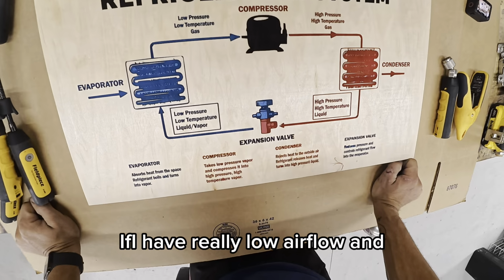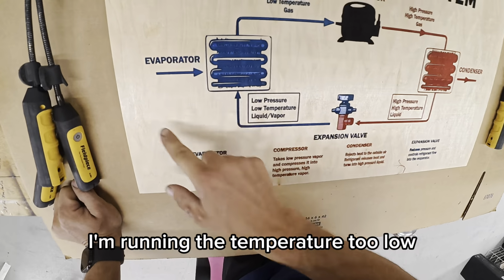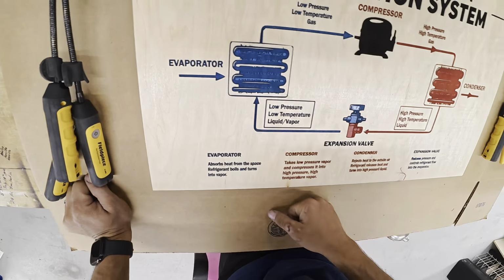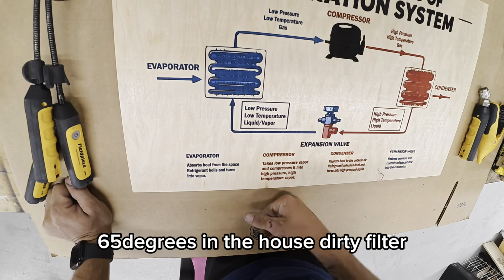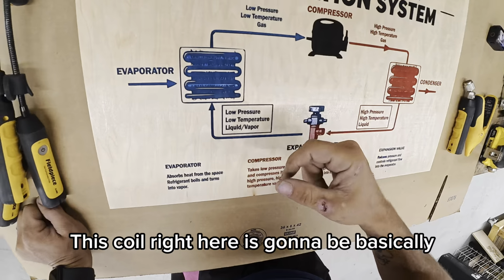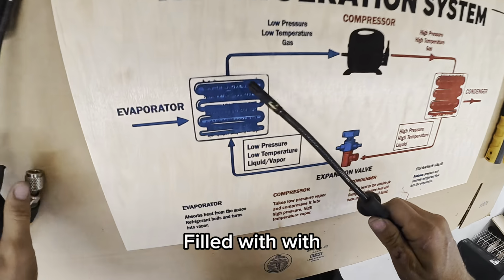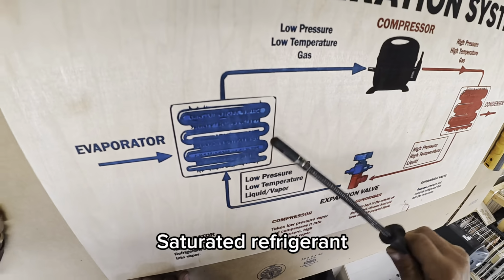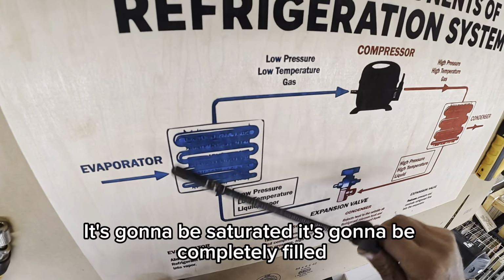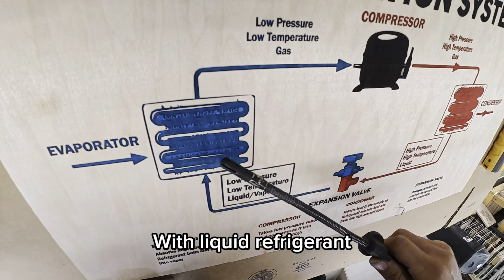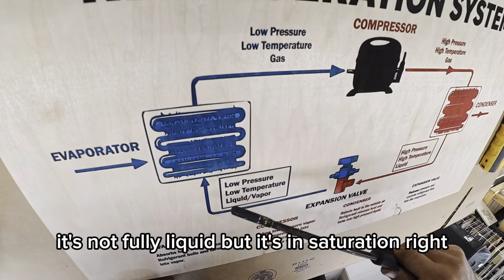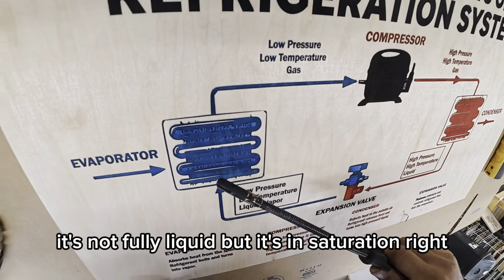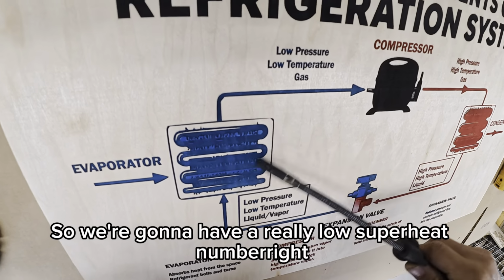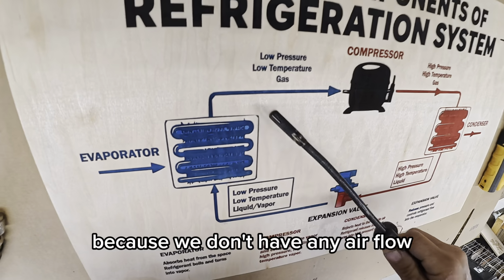If I have really low airflow and I'm running the temperature too low, let's say 65 degrees in the house, dirty filter, this coil right here is gonna be basically filled with saturated refrigerant. It's gonna be completely filled with liquid refrigerant. It's in saturation. It's not fully liquid, but it's in saturation, right? So we're gonna have a really low superheat number, because we don't have any airflow.